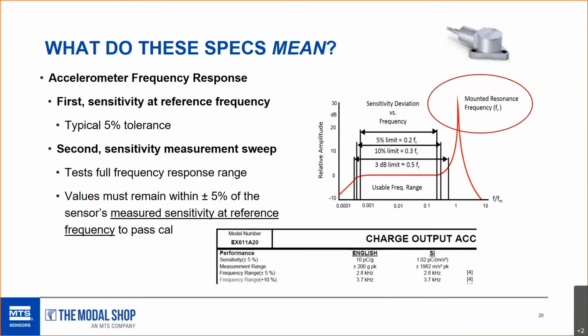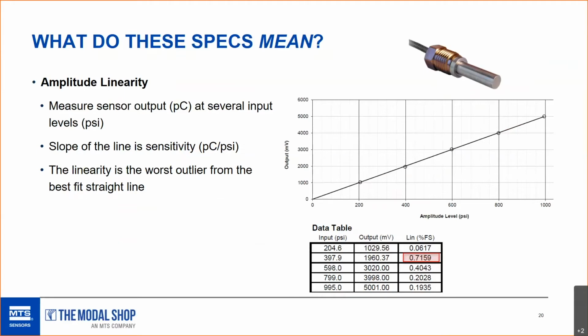And then the mounted resonant frequency, we measure that also quite often. And that's a rundown of the most common accelerometer calibration data. On the pressure sensor side, the common ones are amplitude linearity and again sensitivity, of course. And what you see here is data from a CalCERT of a pressure sensor.